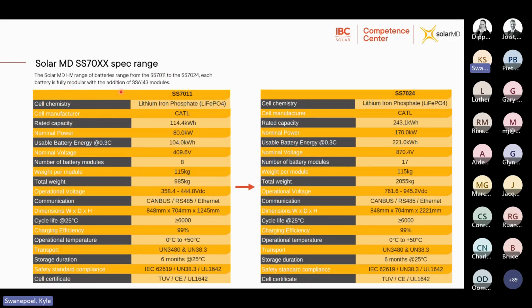Now, the battery module that is used, that is the SS6143, and that is the same as the SS214 in its specification and sizing. It's just the application as well as the faceplate on the battery that is different because it is an HV module. All right, so the SS7011, being the smallest HV battery that SolarMD has, uses CATL technology. It's rated at 114 kilowatt hours. The power rating is 80 kilowatts.